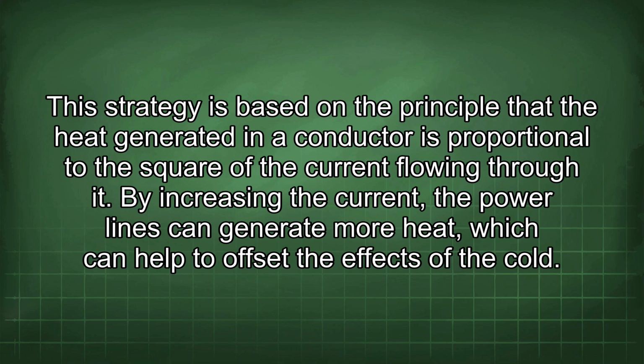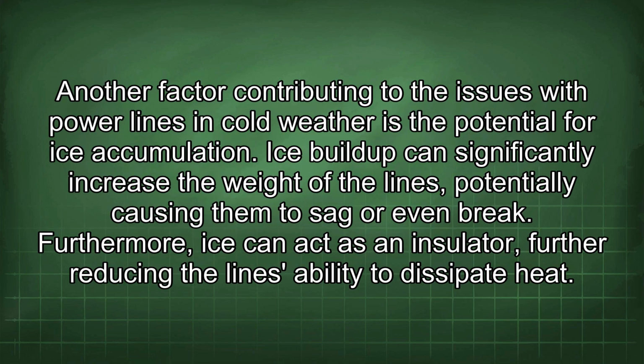This strategy is based on the principle that the heat generated in a conductor is proportional to the square of the current flowing through it. By increasing the current, the power lines can generate more heat, which can help to offset the effects of the cold. Another factor contributing to the issues with power lines in cold weather is the potential for ice accumulation. Ice buildup can significantly increase the weight of the lines, potentially causing them to sag or even break. Furthermore, ice can act as an insulator, further reducing the line's ability to dissipate heat.